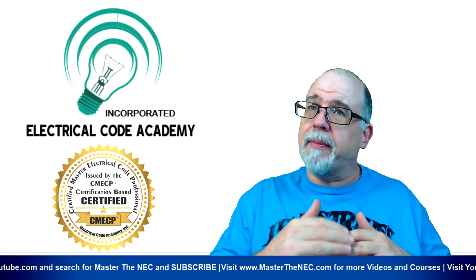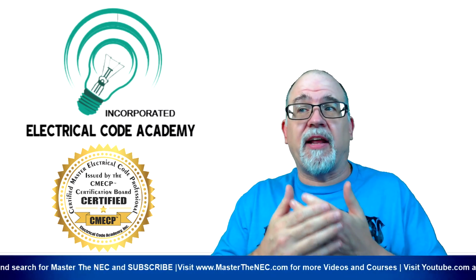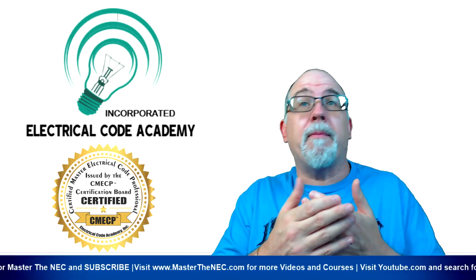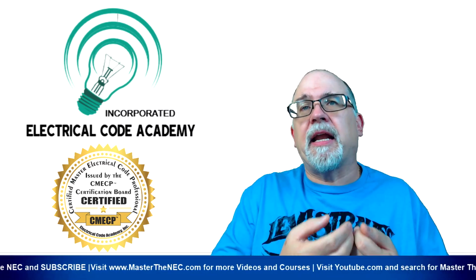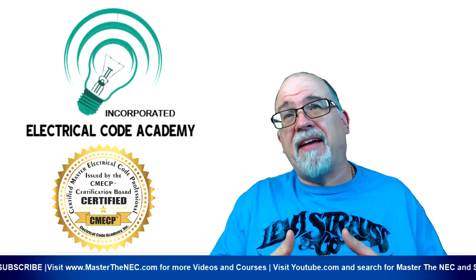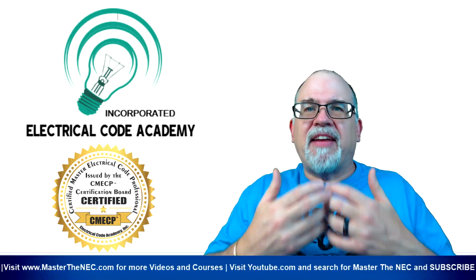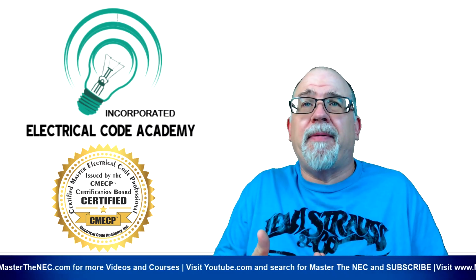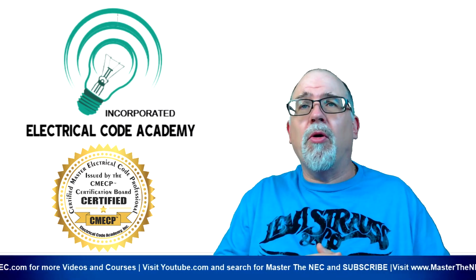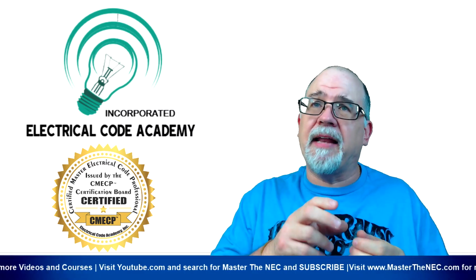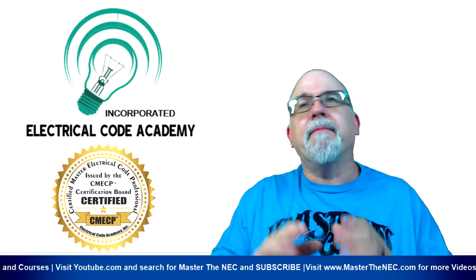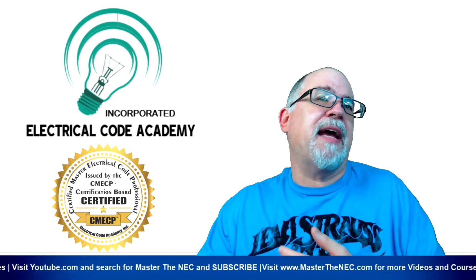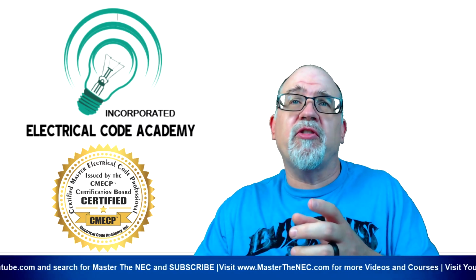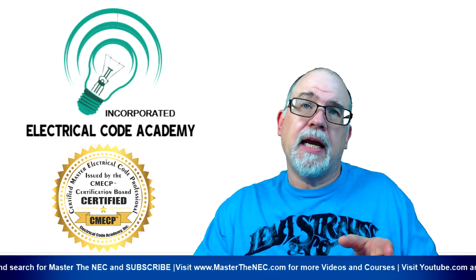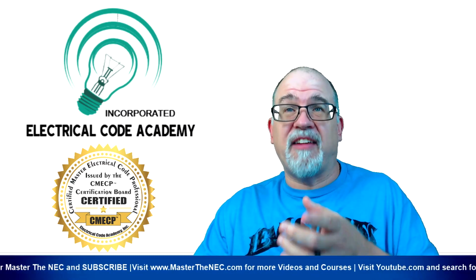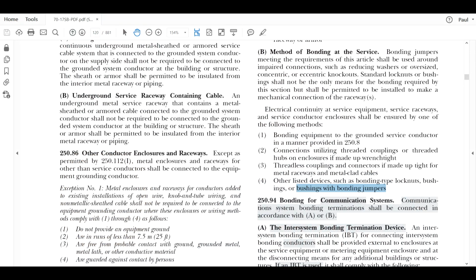So that's what you need to do if you were using the general rule for over 250 volts. Then you're going to use one of these options. And if it does have impaired connections like concentric or eccentric or oversized, then you're going to need a bonding jumper. If they're not going to have that, then you don't need the bonding jumper, but you have to have one of these other aspects. And so typically people use the bushing with the loop through, or they use a bonding bushing with the screw, and they'll bind that screw down into it, and they're perfectly okay. All right, but let's talk about the real world. Most of the time you're not going to run into any of that, and so we're going to use the exceptions here for this application in the 250.97 exception. So let's go back and look at the exception.